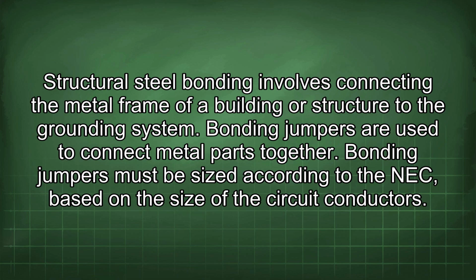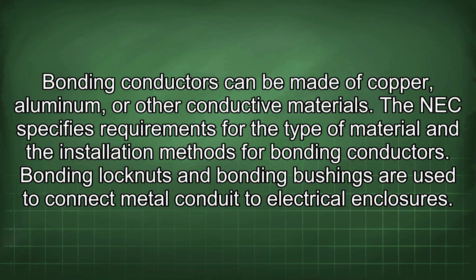Bonding jumpers are used to connect metal parts together. Bonding jumpers must be sized according to the NEC, based on the size of the circuit conductors. Bonding conductors can be made of copper, aluminum, or other conductive materials. The NEC specifies requirements for the type of material and the installation methods for bonding conductors.